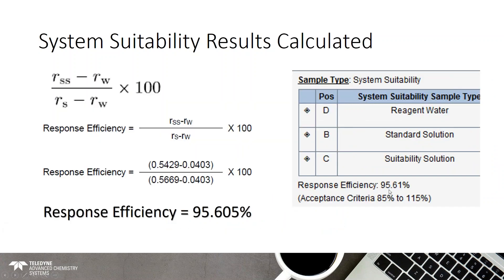Just to verify the system calculated it correctly, I also hand-calculated the response efficiency using the formula given in the method, substituting the values we received. The hand calculation gives 95.605%, which matches the software's 95.61% — it just rounded to the second decimal point. You do not have to do this by hand if you have a Fusion.